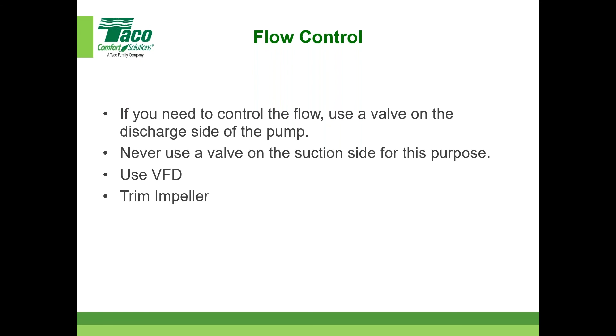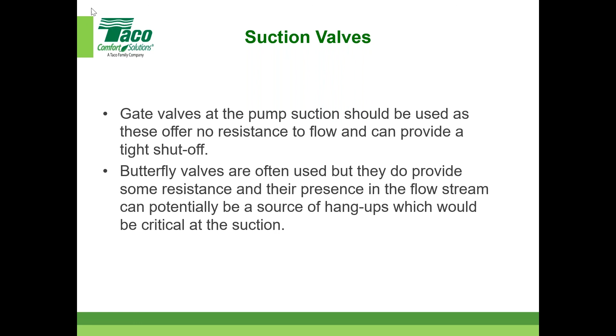Gate valves are nice. Nothing gets hung up. Very little resistance to flow, and they provide a tight shutoff. I mean, butterflies are used a lot, but they do add a little resistance, right? More than a gate valve. Gate's almost wide open, or pretty much is wide open, and sometimes there's a hang up, something can get stuck in there. So that's something to consider in that regard as well.